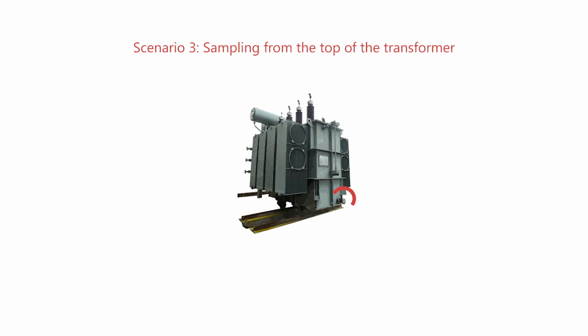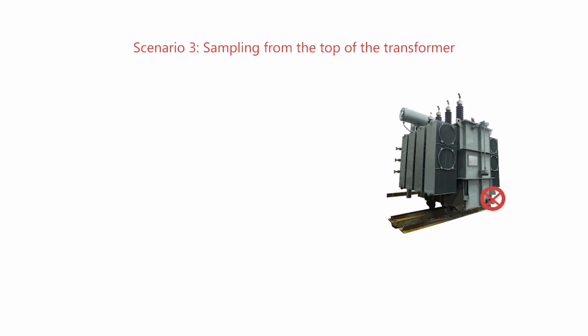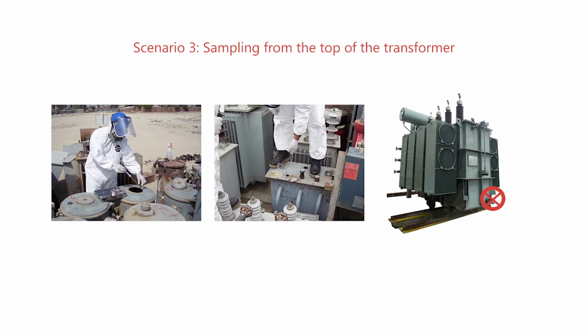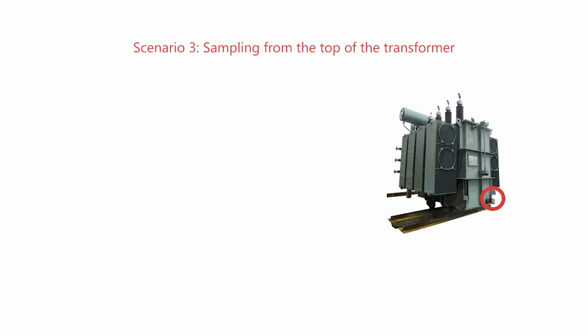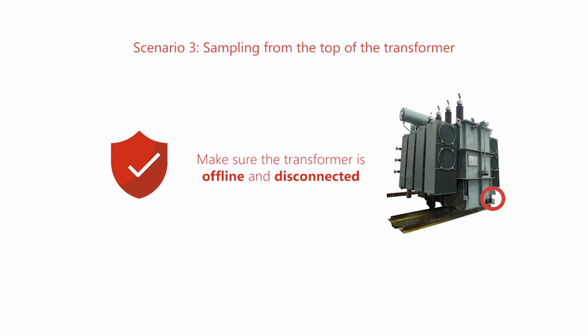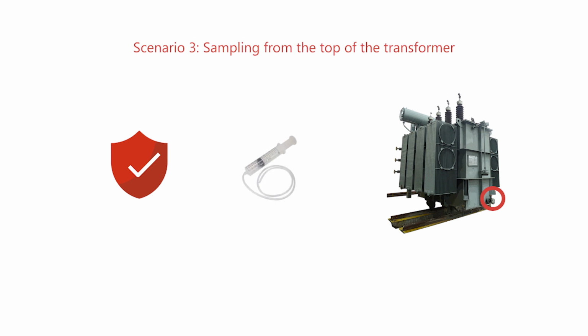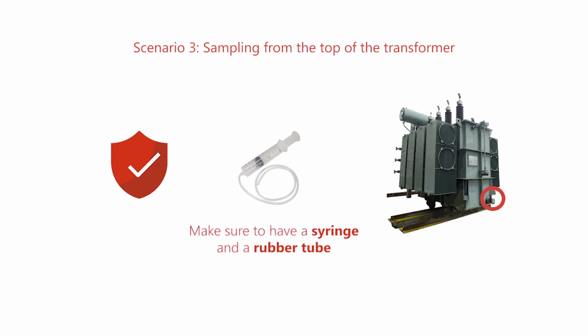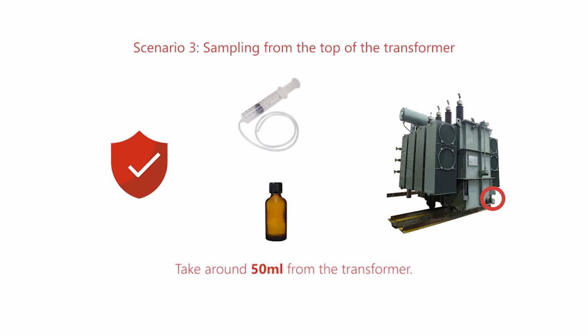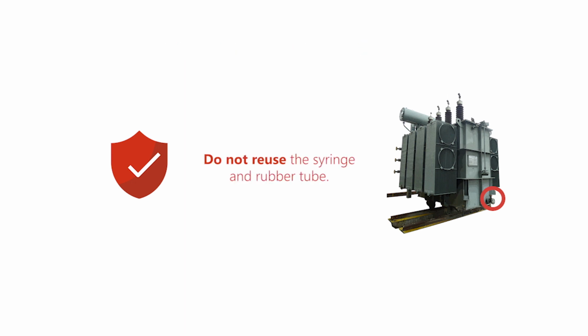In case the drain valve at the bottom of the transformer cannot be used, the sample should be taken from the filling cap at the top of the transformer. This will require additional safety precautions. The transformer will need to be offline and disconnected from the network to collect the sample. In order to collect the oil, a rubber tube and a syringe are needed to take up the oil. Once about 50 milliliters are taken up by the syringe, carefully dispense it into a sample bottle. A new syringe and tube should be used for each sample taken this way.